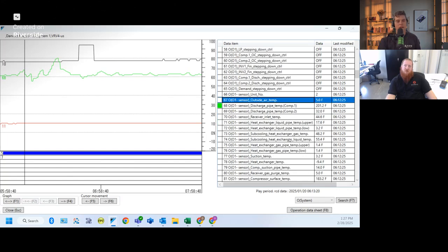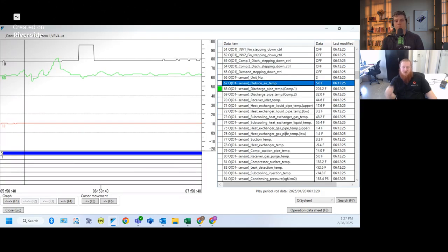No, and so in discharge temperature 2, when you populate it there, I like to go right to the max. If I'm a mountain climber, I want the biggest mountain there is, and I want to go all the way to the top. So when I populate discharge temp, I'm looking for how high it ever gets in this data set, and wherever the highest point is, that's where I'm going. I want the action. And here you can see 242. That's a roasty, toasty compressor, right?